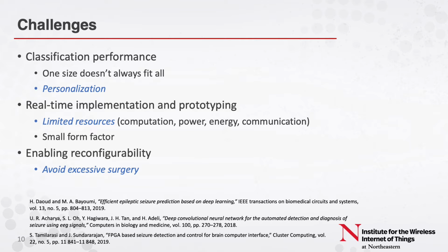Furthermore, once you have a good classifier, you need to take into account the real-time considerations, so the hardware and latency constraints. And this is even more prevalent in our case when the device is implantable because it has to be small, so it can't have large, powerful computers. It'll have really limited resources with limited computational power, energy, and communication capabilities. So it needs to do what it does in a very efficient way, especially the classification part.